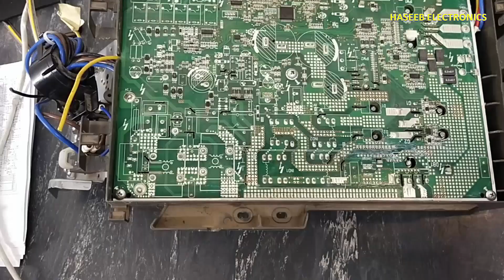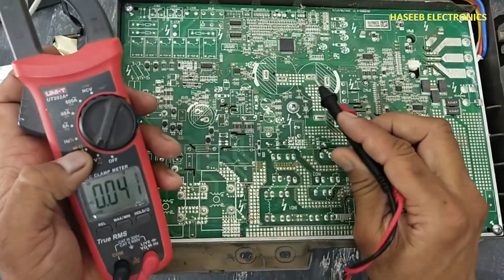cooling fan. Now when we remove this cover, a very important safety point: always check the voltage on these capacitors. Even if it is removed from the unit and not connected to power, always verify the voltage before touching the board. Sometimes this capacitor has voltage. Normally these are charged at 400 volt DC. Never touch the board until you discharge it. After discharging, it is safe to remove.